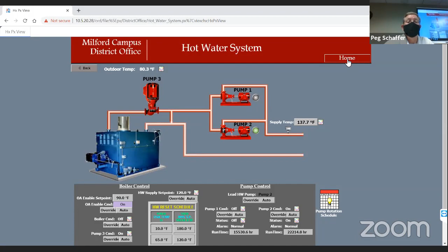That's the heating plant that serves off of an air handling unit. Marvin had passed out a sheet with an AHU—you'll see that acronym. An air handling unit is a piece of equipment that supplies air to the vents in each room, and the air conditioning comes from the air handling unit. There's also gas heat on that unit that allows for morning warm-up heating, but once the morning warm-up is complete, each room can get its own independent temperature control. Instead of one thermostat controlling the entire building, we actually have thermostats in each room so we can separate that control.